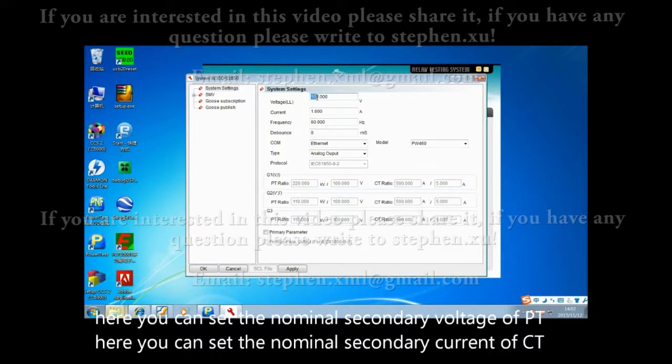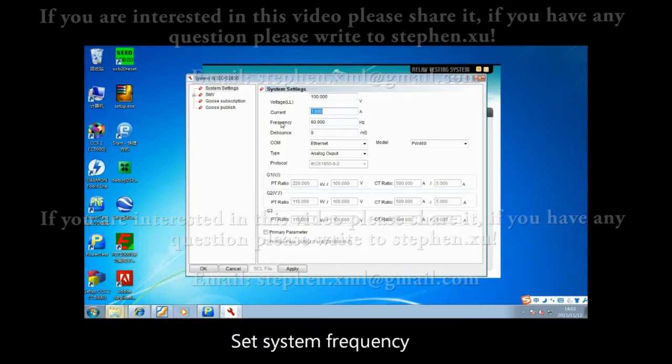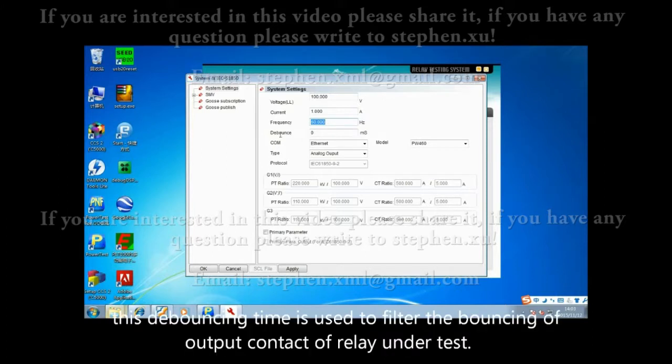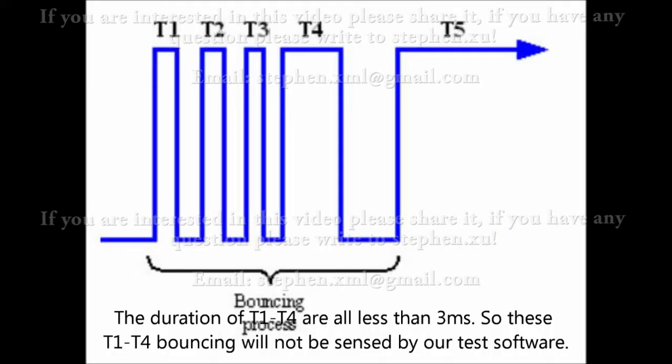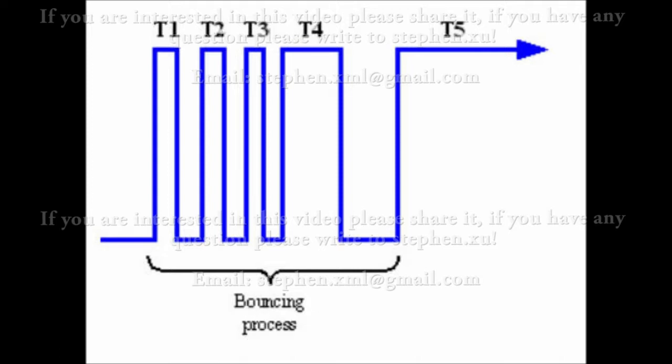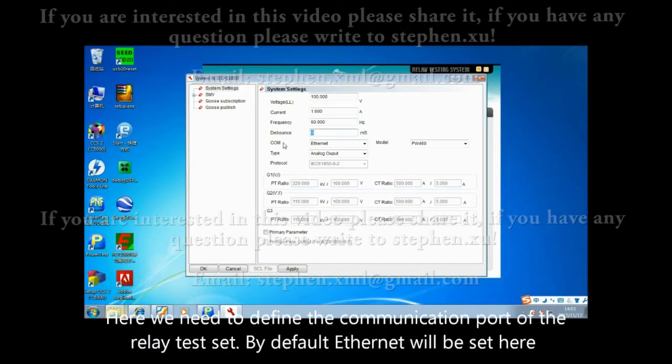Here you can set the nominal secondary voltage of PT and the nominal secondary current of CT. Set the system frequency. This debouncing time is used to filter the bouncing of output contact of the relay under test. The duration of T1 to T4 are all less than 3ms, so this bouncing will not be sensed by the test software.